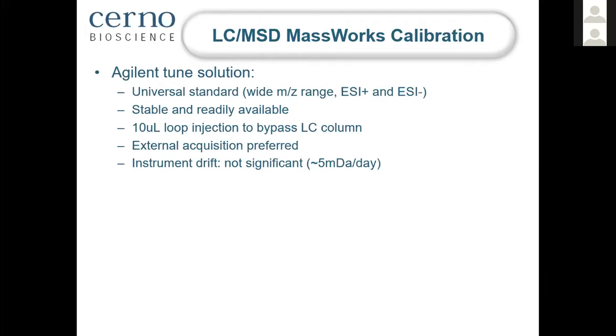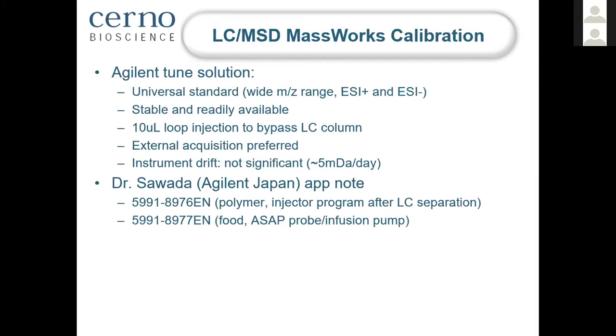The instrument would drift throughout the day, but typically not more than 5 milli-Dalton per day, which is within our error bound. So that's a recommended standard solution to use. Dr. Sawada-san from Agilent Japan has written 2 application notes with some clever ways of introducing the standards. For example, for a polymer application, you can use the injector program after the LC separation to introduce the standard. And for a food application using ASAP probe, you can use an infusion pump to introduce the standard as well.